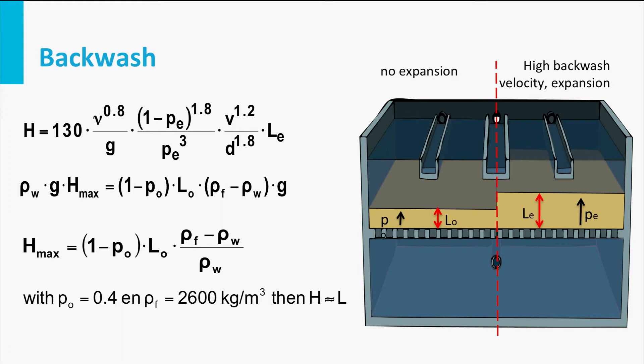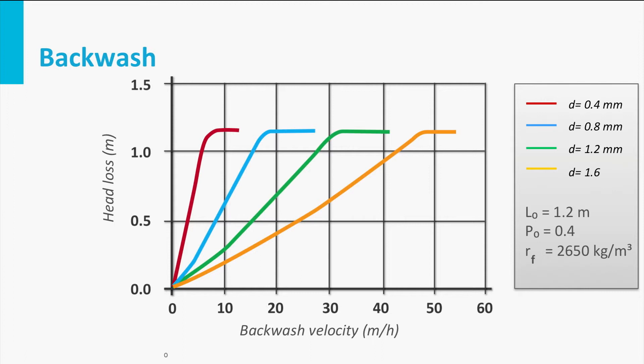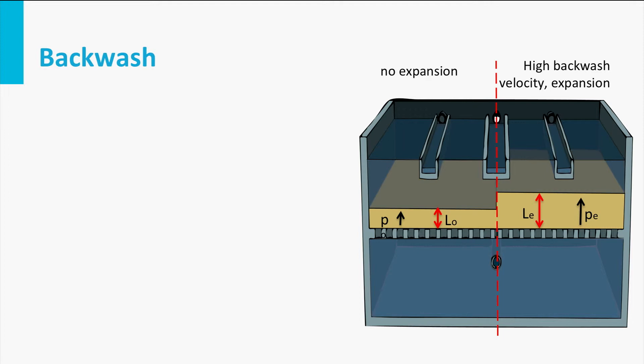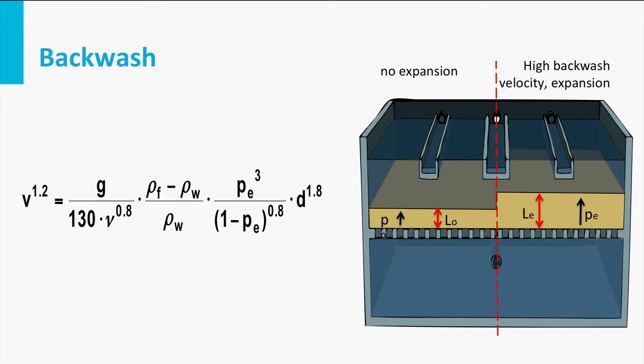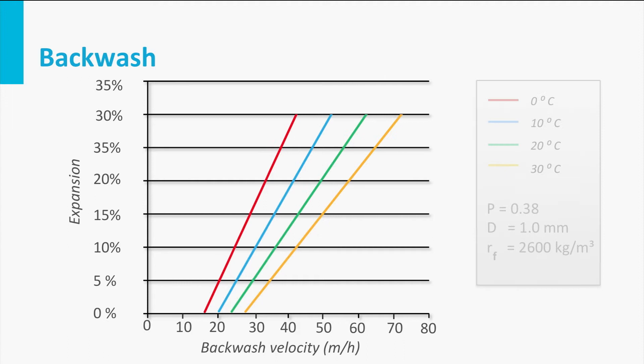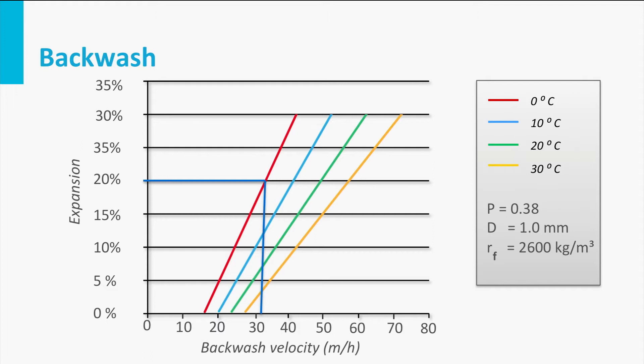The resistance is a function of the backwash velocity, and the maximum resistance is dependent on the grain diameter. The backwash velocity needed to achieve a certain expansion E and the resulting porosity PE can be calculated with a combination of the equations given. To achieve a bed expansion of 20%, a backwash rate of more than 30 meters per hour is necessary — considerably higher than the filtration rate, which varies between 1 and 20 meters per hour.